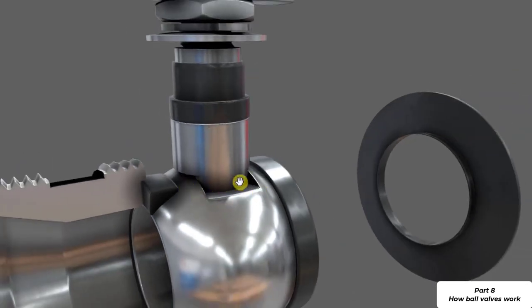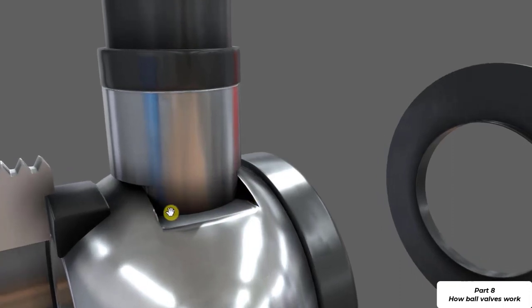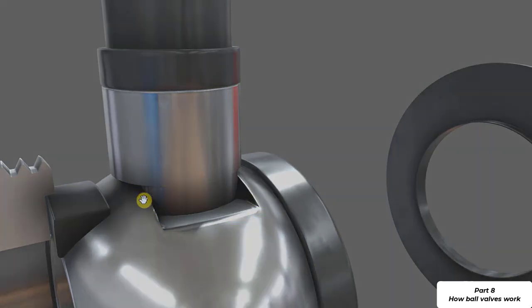Notice that the shape is rectangular and this allows us to apply a high amount of torque without deforming the top of the ball valve. When I talk about deforming or deformation I mean rounding off the top of the ball valve. So we've got quite a large area for the stem to come into contact with the ball so we don't run the risk of rounding the top of the ball valve which would mean then that we can't turn the ball anymore.